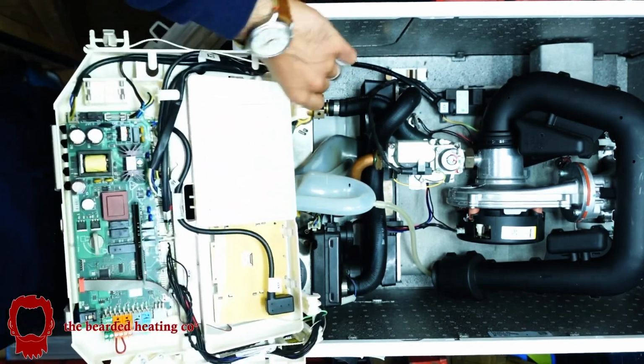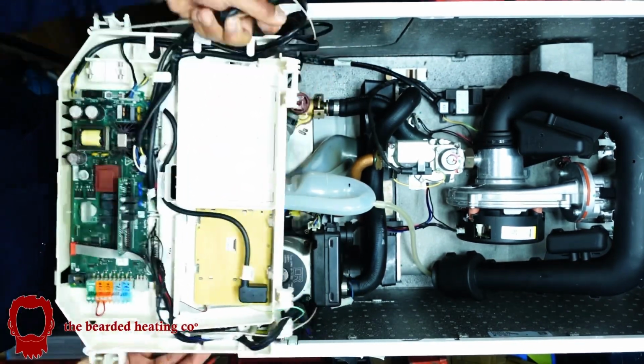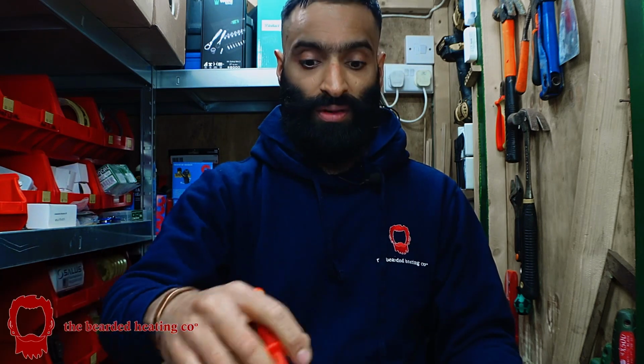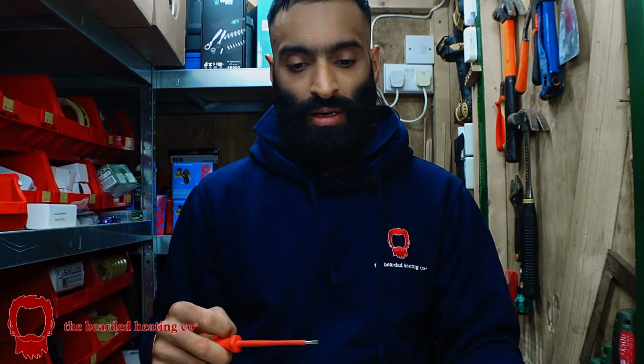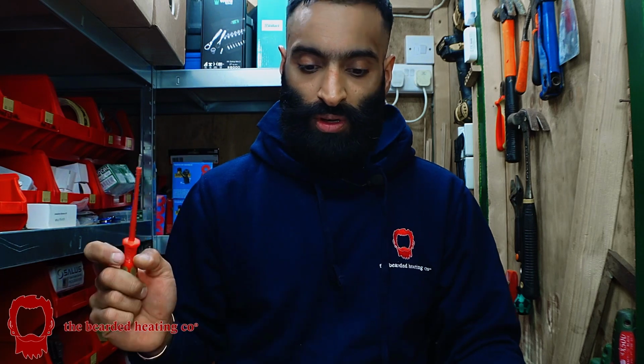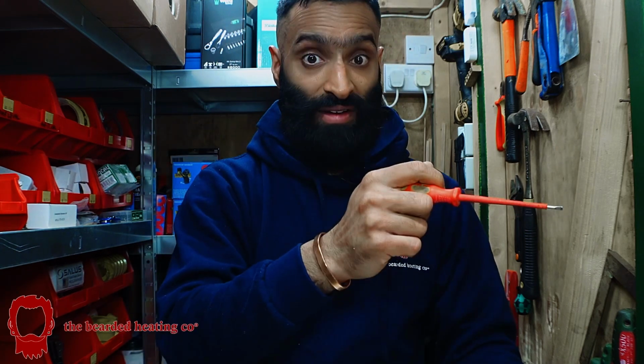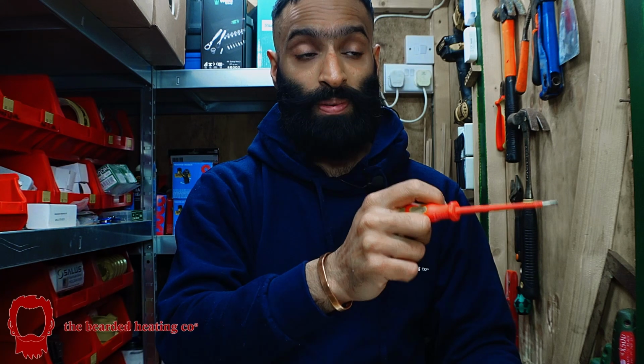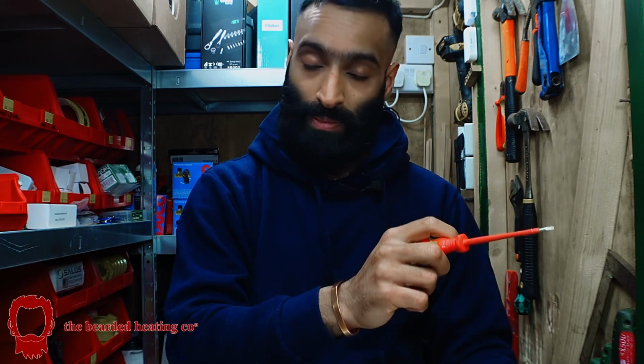So what I'm going to do is take it all out. Because this boiler was working when I took it off, other than having a pinhole, I am going to salvage all the parts and keep them just in case I go to a job where it's some elderly customer - like the one I had yesterday on the 2nd of April, where the heat exchanger on the Avanta is pinholed. The Avanta I have here that I'm going to strip had a heat exchanger that was actually pinholed as well.